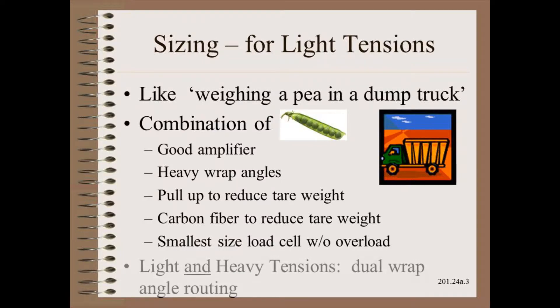Another related challenge is to accommodate a very wide range of products. Here we can have a dual routing of the web to give a high wrap angle for light products for maximum sensitivity and a low wrap angle for heavy products so that you don't need to upsize the load cell. Alternatively, you could have two different load cells and routings, but that is electrically and mechanically more costly.